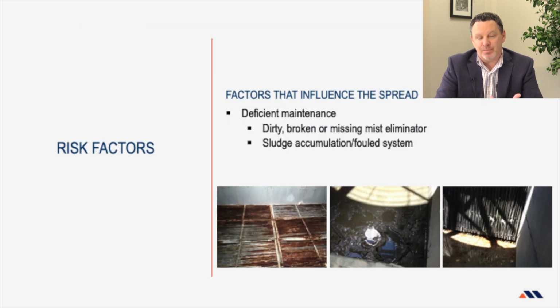One of the best examples we have is if you have a cooling system for a standard HVAC system for your building, and you have 3 or 4 chillers, but the temperature is not so hot outside, so you're only running 1 or 2, so you've got 1 or 2 that are on standby. Well, those represent significant risks for being stagnant water and need to be managed to reduce the risk.